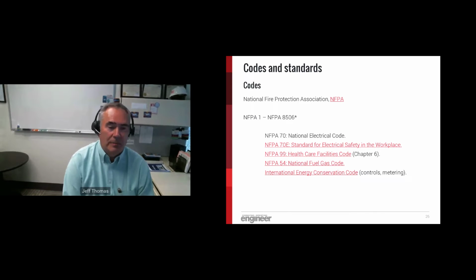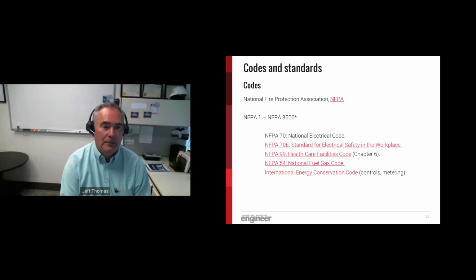Some of the codes that we play with all the time are pretty much all under the umbrella of the National Fire Protection Association. National Electric Code just happens to be Chapter 70 of the NFPA. Then we've got 70E for electrical safety. I mentioned 99 for Healthcare Facilities Code. Anybody who does electrical work in healthcare facilities will be very familiar with Chapter 6 of 99. There's also NFPA 54, the Fuel Gas Code.